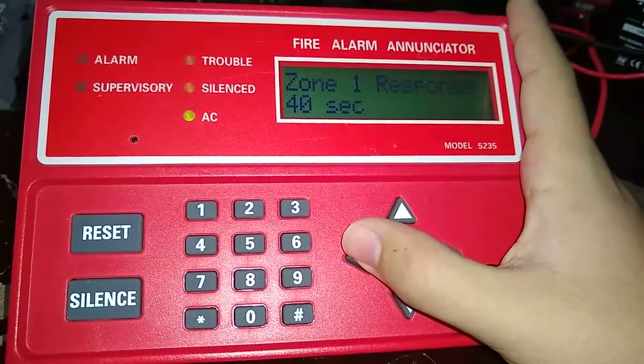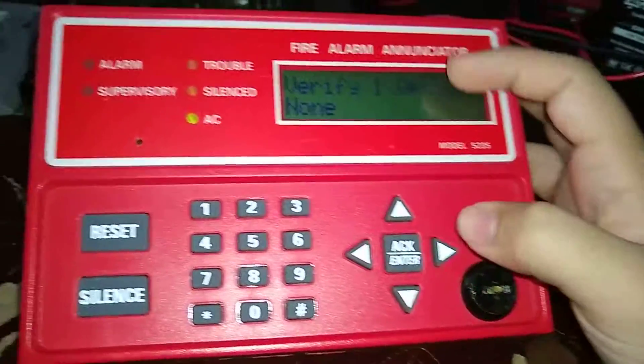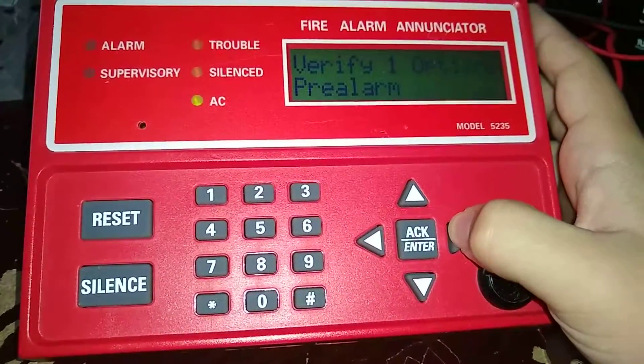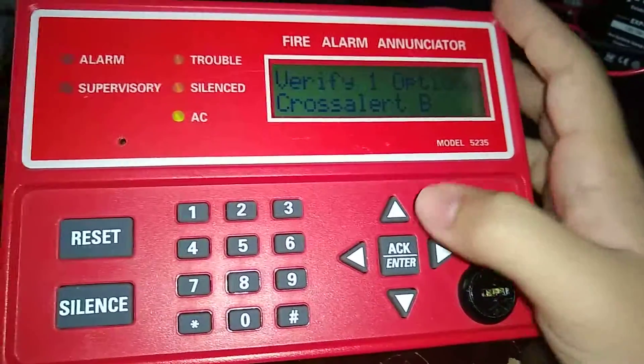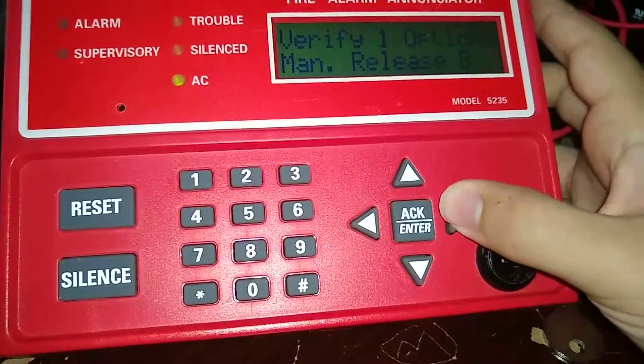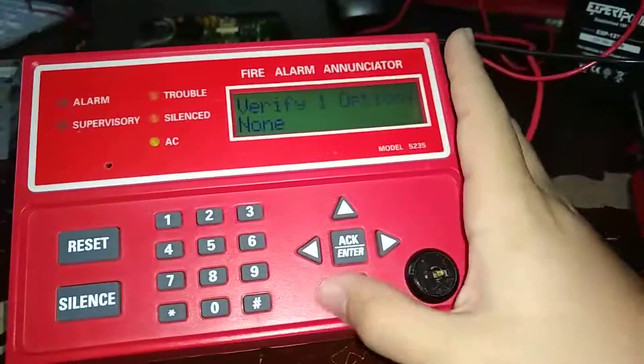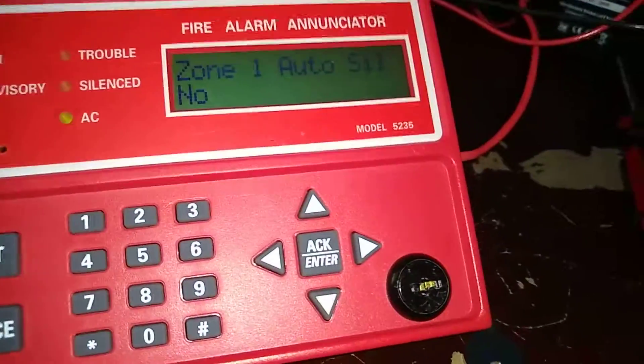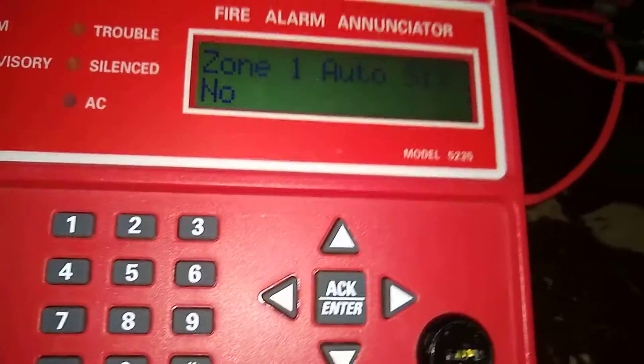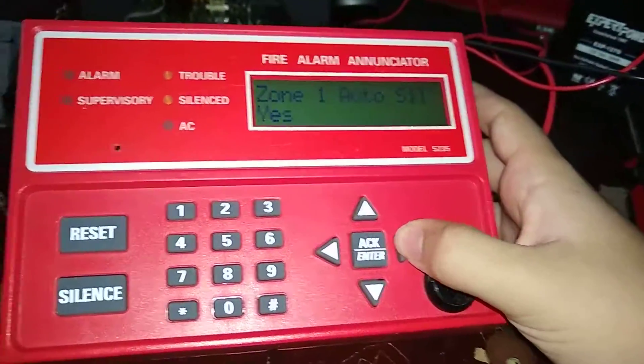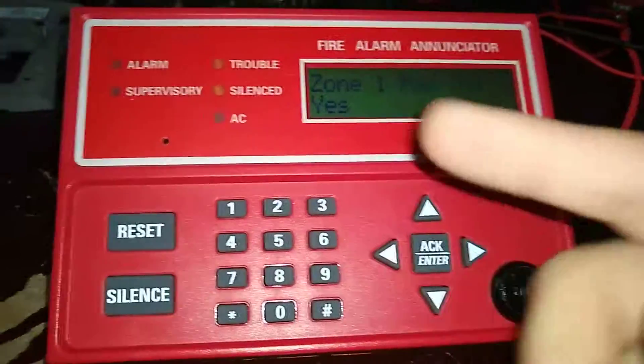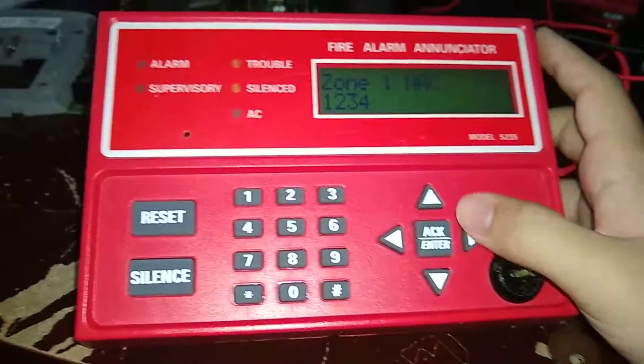Verified options — that is for smoke detectors: pre-alarm, enhanced smoke, cross alert. You guys won't need that. Interlocks or manual release — that's for your sprinkler systems. Zone one auto silence: do you want the panel to automatically silence the alarm after a specific amount of time? I have it set to no. Manual silence — meaning you have to silence it yourself — I have that set to yes.